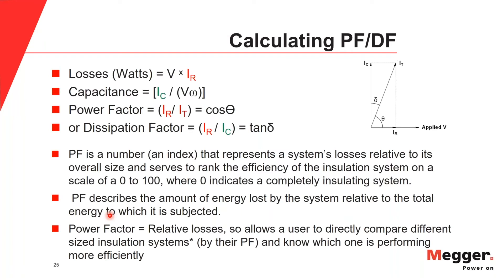Power factor is calculated by the ratio of real current divided by total current. Looking at the vector diagram, that's the same as the cosine of the angle that separates them. Dissipation factor — also known as tan delta — is simply resistive current over capacitive current. Power factor is dimensionless — it's an index that represents the system's losses relative to its overall size. Power factor is able to rank the efficiency of an insulation system on a scale from zero to one hundred percent, where zero would indicate a completely insulating system. It describes the amount of energy lost by the system relative to the total energy to which it's subjected.